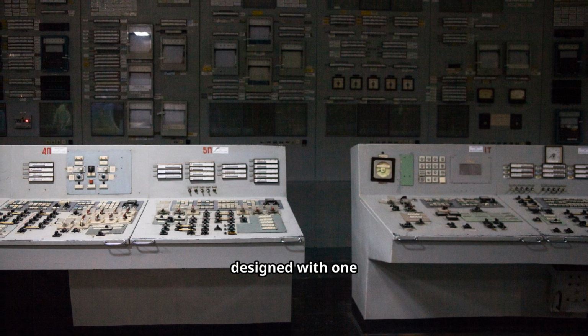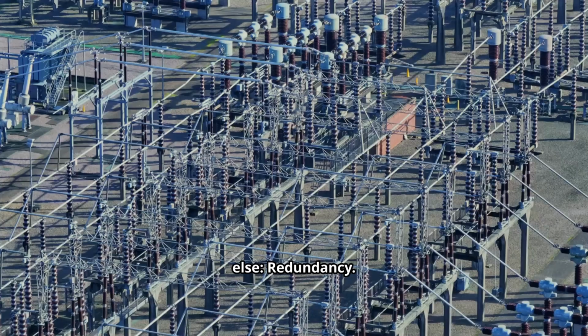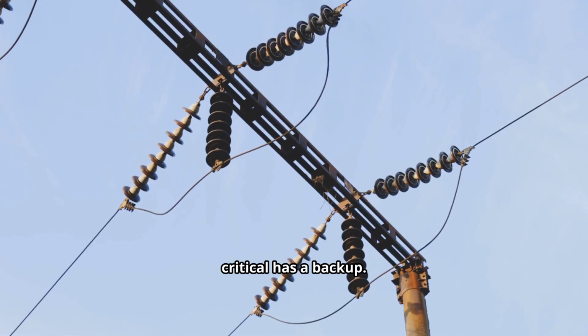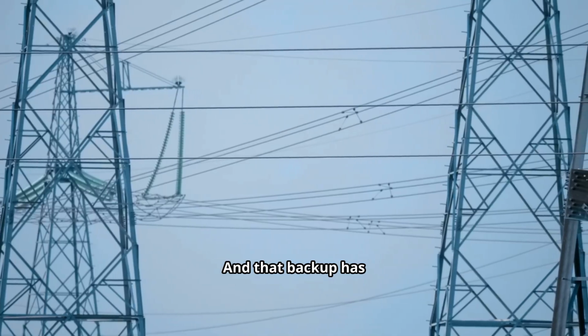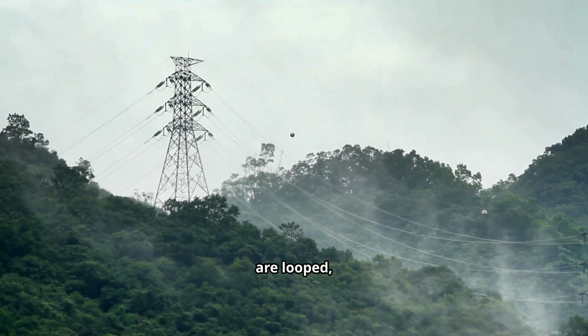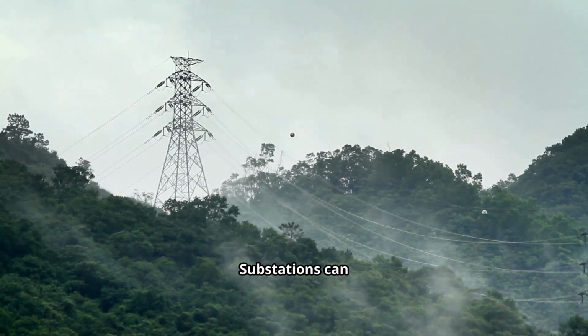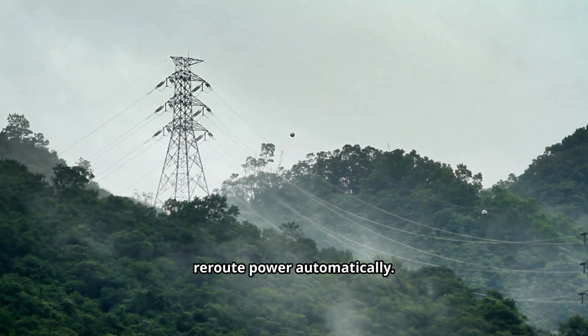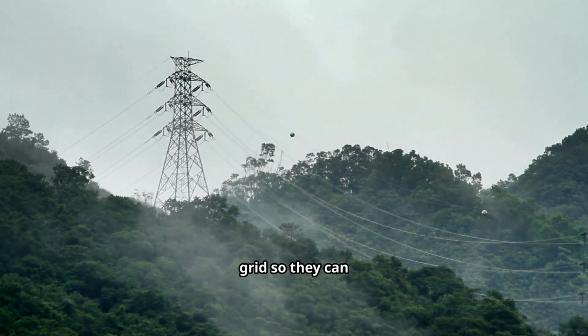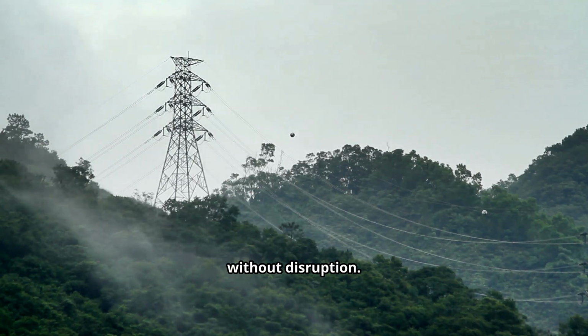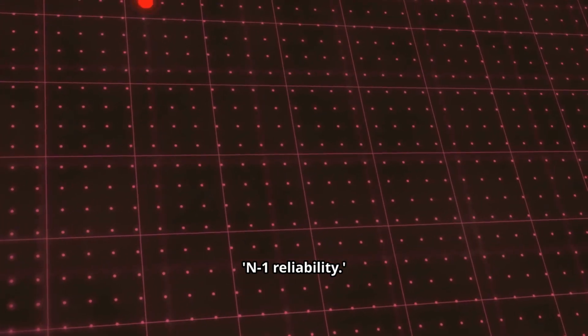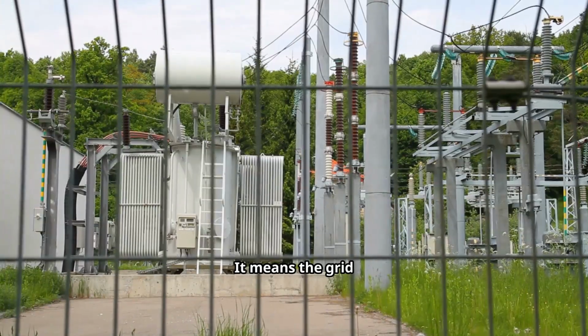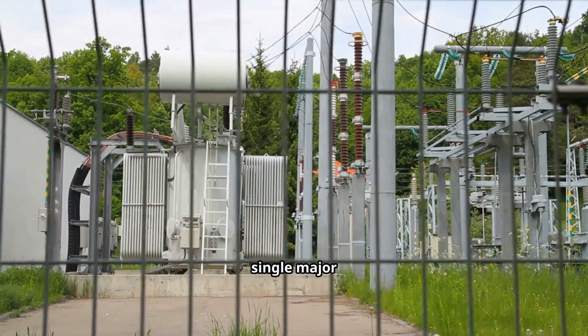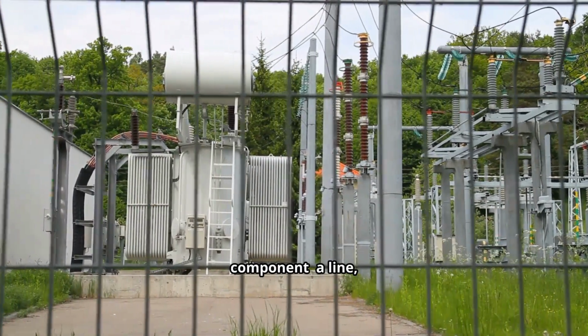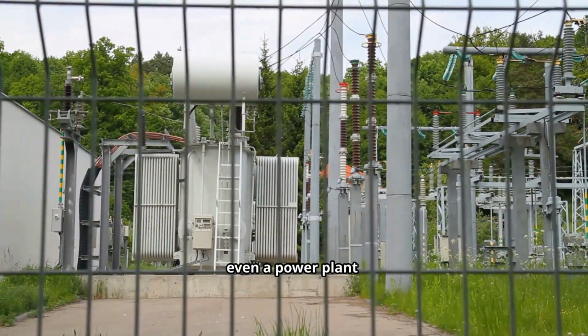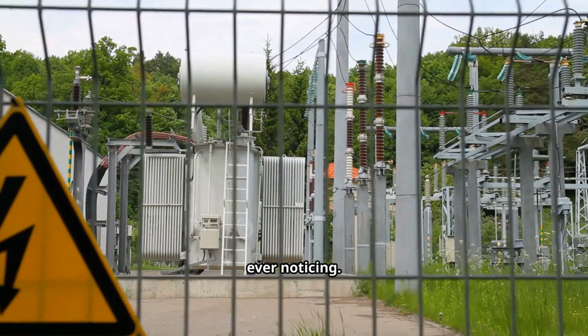Power grids are designed with one principle above all else: redundancy. Almost everything critical has a backup, and that backup has a backup. Transmission lines are looped, not straight. Substations can reroute power automatically. Generators synchronize to the grid so they can drop in or out without disruption. This is known as N-1 reliability. It means the grid must survive the failure of any single major component, a line, a transformer, even a power plant, without customers ever noticing.